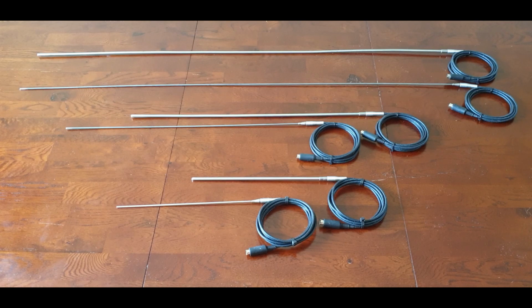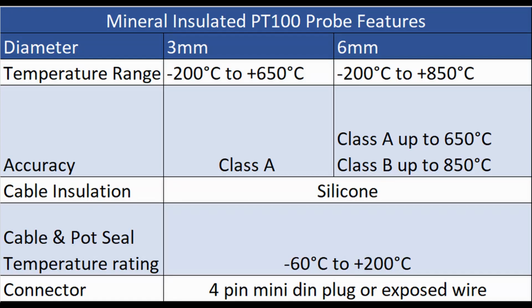In terms of specification, it uses a PT100 ohm element, and the sheath material is a mineral insulated stainless steel. In terms of temperature range, the 3mm diameter one has a temperature range of -200 to 650 degrees Celsius, and the 6mm diameter one has a temperature range of -200 to 850 degrees Celsius. In terms of accuracy, the probes follow a Class A tolerance between -200 to 650 degrees Celsius. The 6mm diameter probe from 651 degrees Celsius to 850 follows a Class B tolerance. The cable insulation is silicone, and the cable and pot seal have a temperature rating of -60 to 200 degrees Celsius. In this particular case, it's terminated in a 4-pin mini DIN plug, but as we said, we also supply them without a connector.